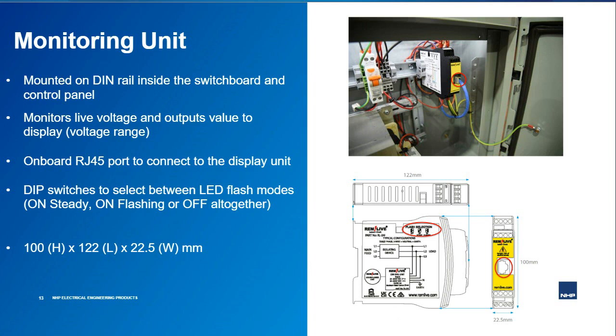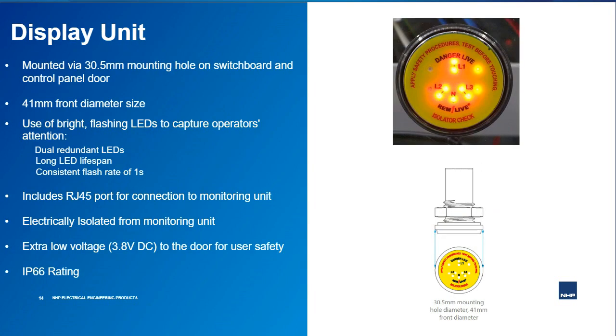The unit has a standard size that you would expect of an electrical component used inside a panel or a switchboard. Its dimensions read as 100mm high, 122mm in length, and 22.5mm in width. Then we have the display unit. This is mounted by creating a 30.5mm circular hole on the front panel and is secured by the locking nuts which are pre-supplied with it. And the surface area of the display unit measures 41mm in diameter.